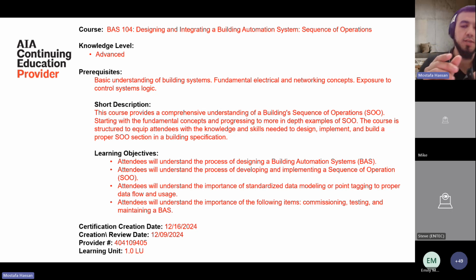And the focus here is standardized, right? One person can define it one way, another can define it another way. So we're going to look at today the importance of standardizing this data as a benefit to the building owner or operator. And then to end off, we're going to look at things like commissioning, testing, and maintaining a building automation system. Because once the project's delivered, we want to make sure this thing is actually going to function the way that it's programmed, the way that it's sequenced, and that the equipment is tested and calibrated beforehand, before it goes off to the customer.